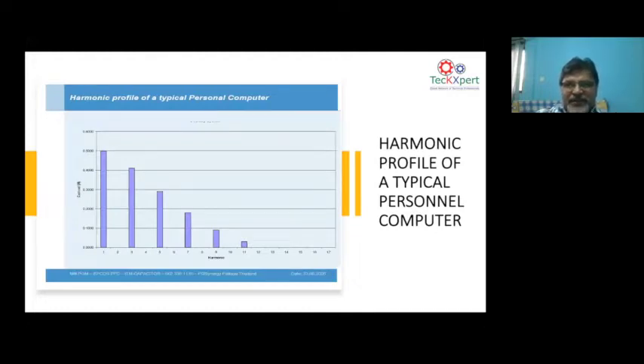Again, as I said at the beginning, characterizing is all about how you define the problem. Now, the waveform you just saw in the time domain in the previous slide, if you convert that into the frequency domain, you will see it has a spectrum of frequencies. The fundamental frequency is number 1. The third harmonic, that is 3 times 50, is 150 cycles. The fifth harmonic is 250 cycles. So this is what the spectrum of a typical computer, fax machine, or LED will look like. It will be predominantly third harmonic, followed by 5th, 7th, 11th, 13th. Go to the next one.